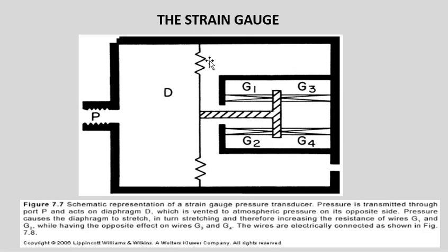So it's a box containing a little box inside, and the box is split into two by a flexible membrane. The left side is fluid-filled, saline and blood at the end of the line to receive the fluctuations in pressure due to a patient's heartbeat. The right side of the box is air-filled, and it's open to air by this little port. And inside is a little electric circuit, such that it consists of 4 resistors attached to this little plunger.